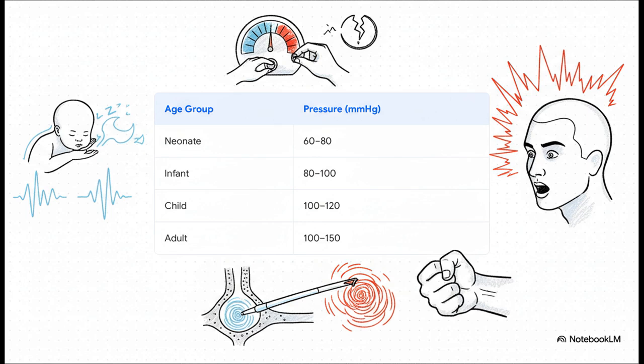A neonate can only handle 60 to 80 mmHg of pressure. That is an incredibly gentle pull. An adult can handle up to 150. If you accidentally used adult-level pressure on an infant, well, you could cause serious trauma, bleeding, you name it. This isn't just about flicking a switch. It's about meticulously calibrating the machine for every single patient, every single time.